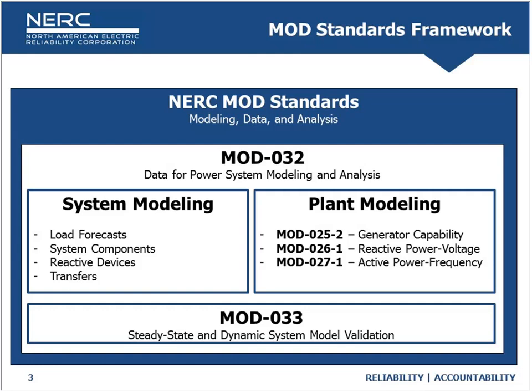When it comes down to what we're talking about today, it's really the plant modeling — which is MOD-25, MOD-26, and MOD-27. MOD-25 is the generator reactive capability, testing which proves you can get to your Pmax, Qmax, Qmin, and Pmin values via test. MOD-26 and MOD-27 are the dynamic model validation or model verification standards, where you go into the plant, perform a verification of some sort, and provide a report showing that the model reasonably matches what's actually installed in the field.